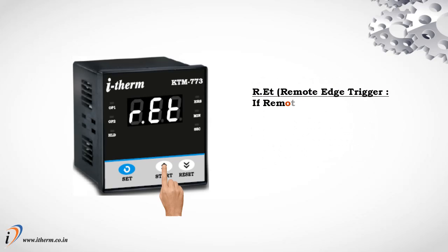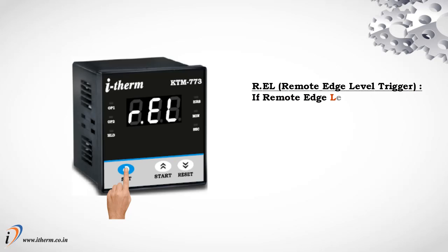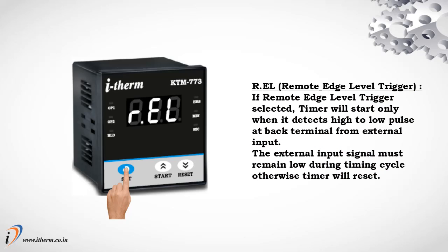Remote Edge Trigger: if selected, timer will start only when it detects a high-to-low pulse at the back terminal from external input. Remote Edge Level Trigger: if selected, timer will start only when it detects a high-to-low pulse at the back terminal from external input, and the external input signal must remain low during the timing cycle, otherwise the timer will reset.